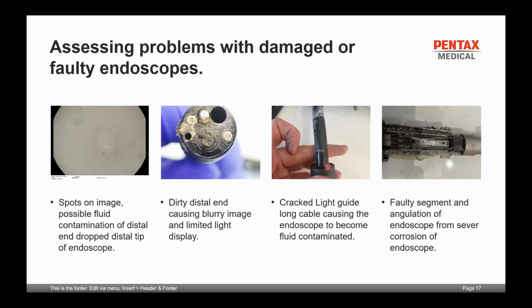Sometimes with usage of chemicals, you come across the drying of either the insertion tube or the light guide section of the endoscope, where you see cracked or perforated marks on your insertion tube or in the polyurethane. That in turn will then cause the endoscope to leak, which will then in turn, if undetected, go across into major fluid contamination and potentially an endoscope looking like that.